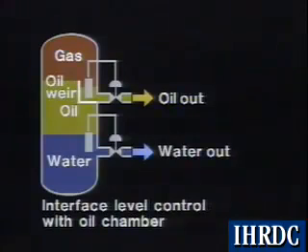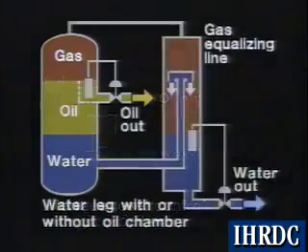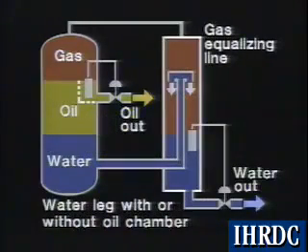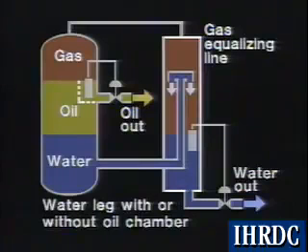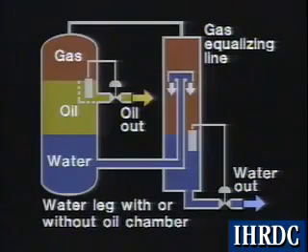The third method uses two weirs, which eliminate the need for an interface float. The interface level is controlled by the height of the external water weir relative to the oil weir or outlet height. This is similar to the bucket and weir design used for horizontal separators.